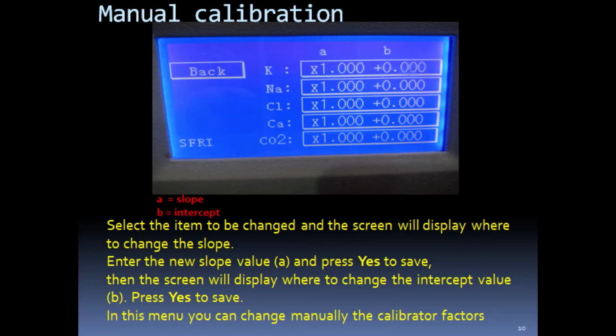On the other hand, if manual calibration is preferred, press Manual from the menu and it will display the slope and the intercept as shown on the screen. Select the item to be changed and the screen will display where to change the slope. Enter the new slope value, which is A, and press Yes to save. Then the screen will display where to change the intercept value, which is B. Press Yes to save. In this menu, you can change the calibrator manually.